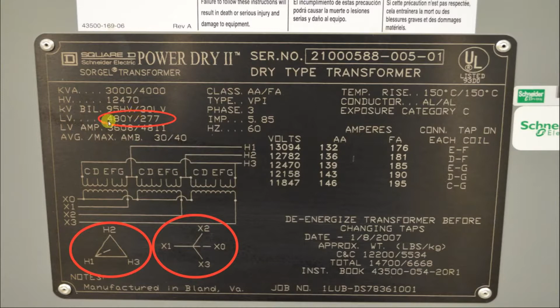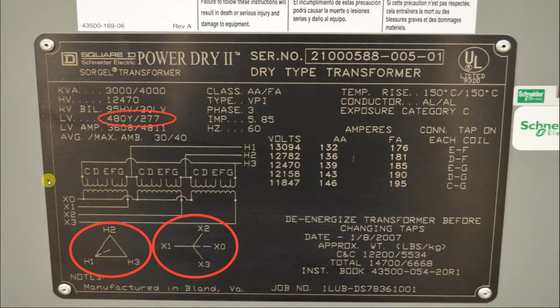The other thing I wanted to note here is we see now why it said 480 volts Y. At least that portion of it we understand. We're still trying to figure out why it says 277 here; we'll get into that in just a moment. But we know that this Y denotes our secondary side is a Y connection. The other things I want to note on here is my 12,470 volts has an abbreviation of HV for high voltage, which we talked about on the previous slide, and my 480 volts is my low voltage side.